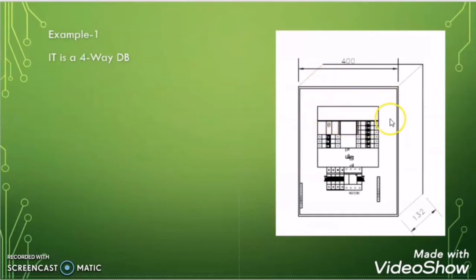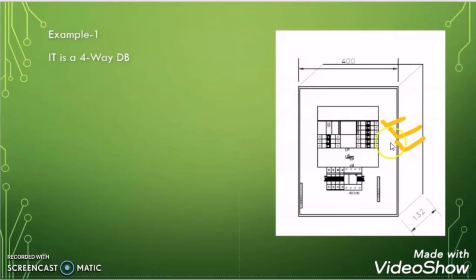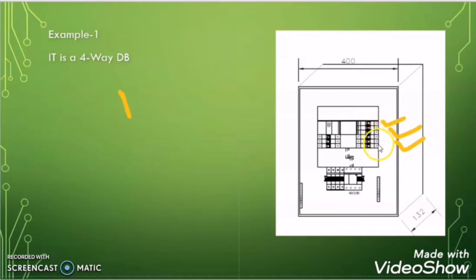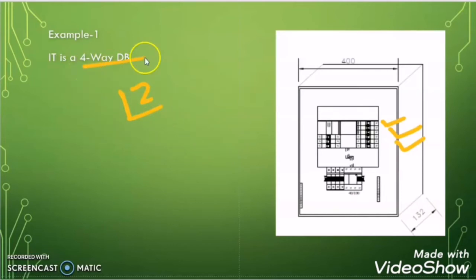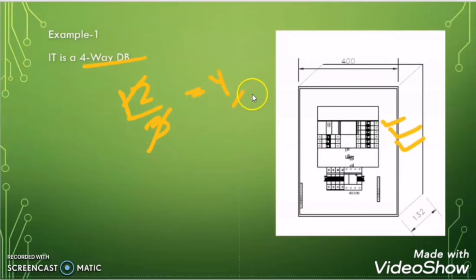Here I have taken a way type FDB final distribution board. It is way type because all the breakers are assembled in a vertical manner. To understand which way it is — 4 way, 6 way, 8 way, or 12 way — we count the number of breakers. Counting gives 12 breakers total. To find the number of ways, we divide by 3, giving 4. So this is a 4 way breaker.